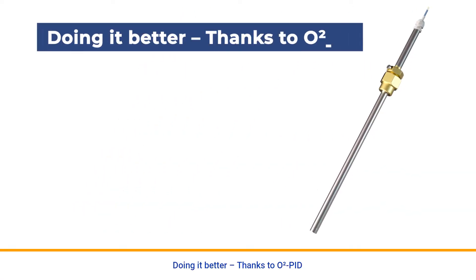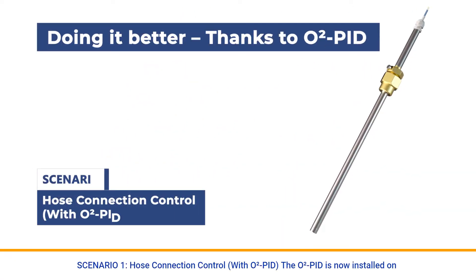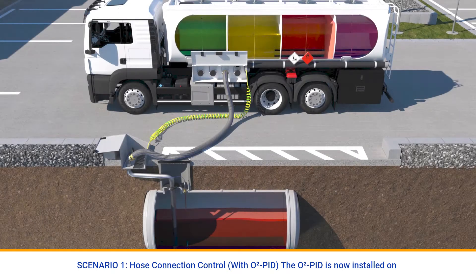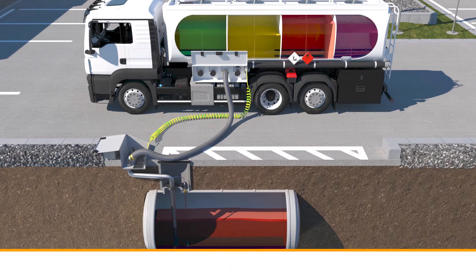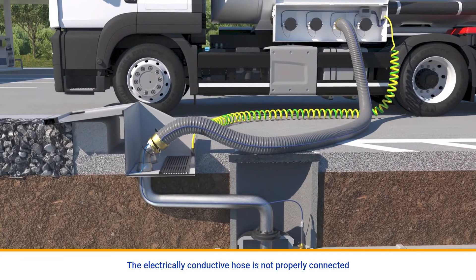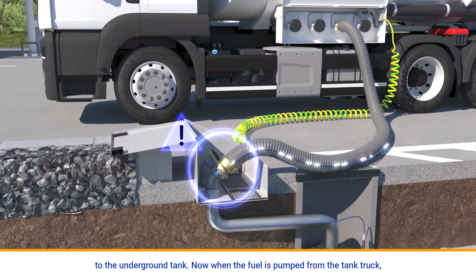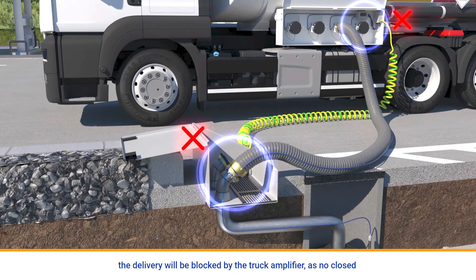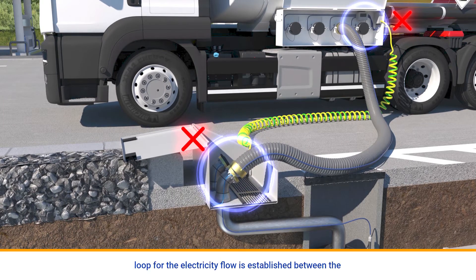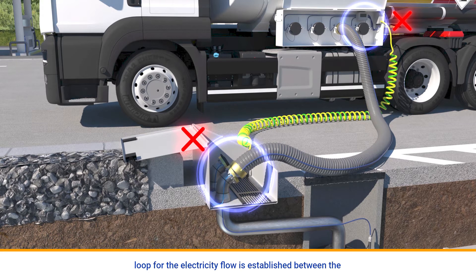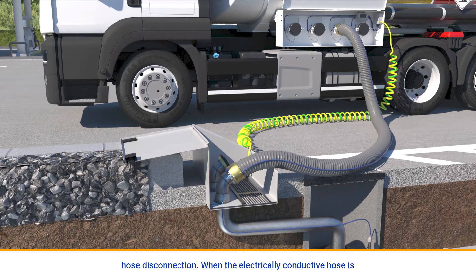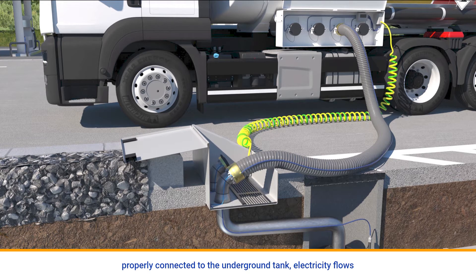Doing it better — thanks to O2PID. Scenario 1: Hose connection control with O2PID. The O2PID is now installed on the tank with proper electrical connections to the underground tank delivery inlet. The electrically conductive hose is not properly connected to the underground tank. When the fuel is pumped from the tank truck, the delivery will be blocked by the truck amplifier, as no closed loop for electricity flow is established between the truck amplifier and the delivery inlet, indicating a hose disconnection.